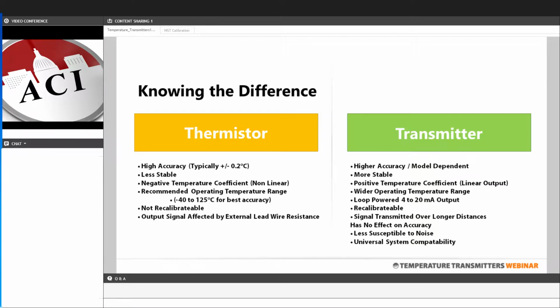And one of the main benefits of using a transmitter is it has universal or near universal system compatibility. Nearly every control system can accept a 4 to 20 input. We know that there are dozens, if not hundreds of different types of thermistors out there, all of them having different curves and different resistance values. And most controllers that accept a thermistor input are very specific. They can only accept one type, and that's it. So with the transmitter, you have near universal system compatibility.